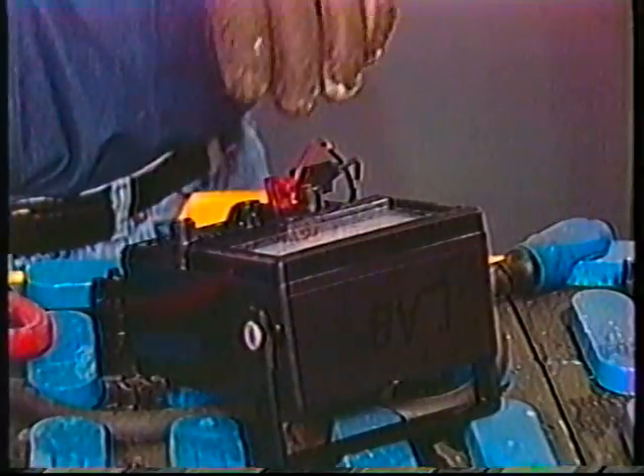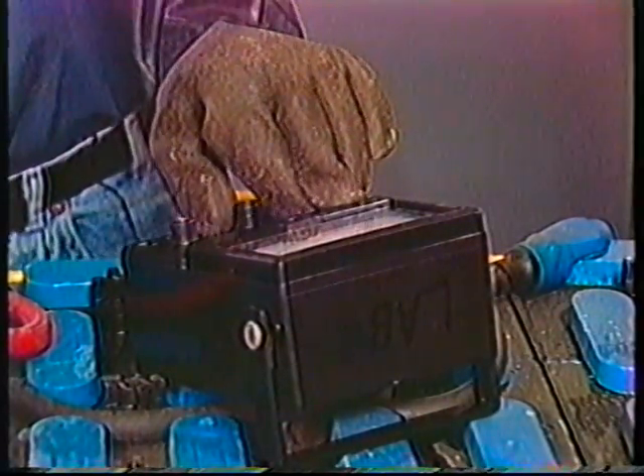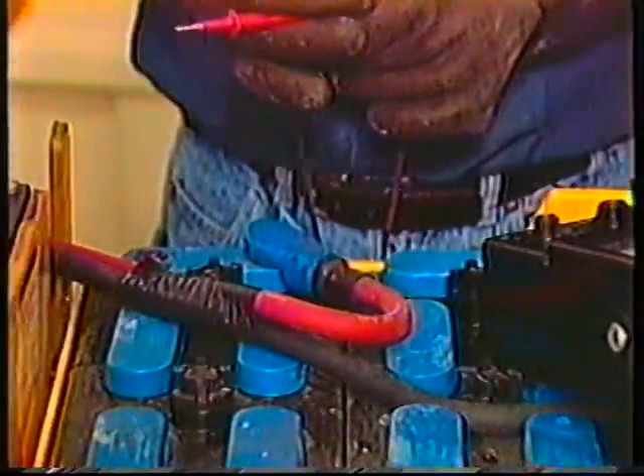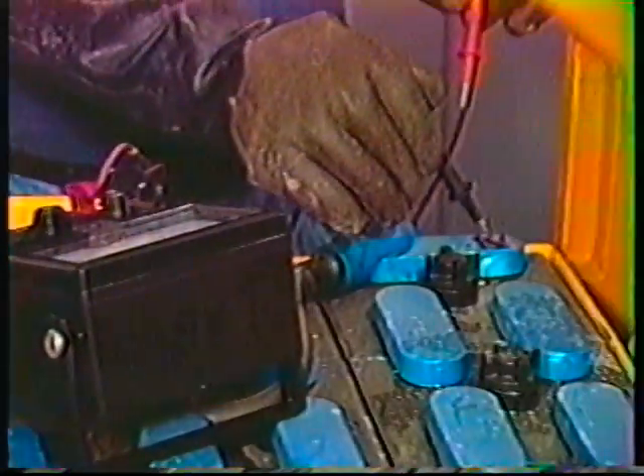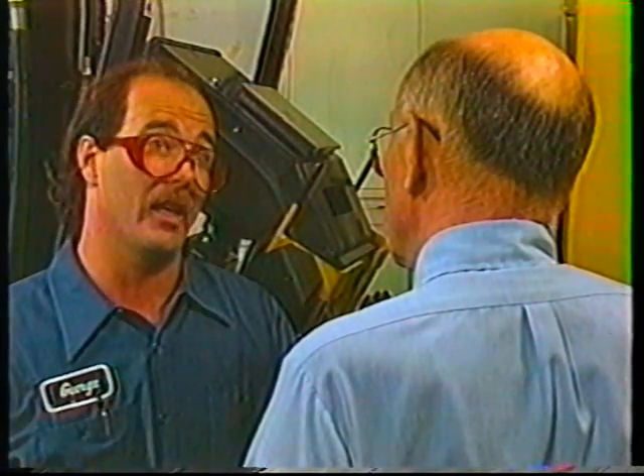To begin the current leakage test, set your volt-ohm meter to the 500 milliamp scale. We need to first get readings from the positive terminal to the truck's frame, like this. Then repeat this procedure from the negative terminal to the frame. In both cases, we're looking for readings less than 100 milliamps. Well, from the positive terminal to the frame, I got a reading of 75 milliamps. From the negative terminal to the frame, I got, let's see, 170 milliamps.